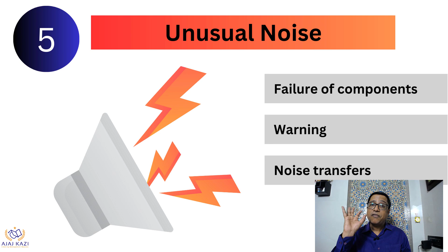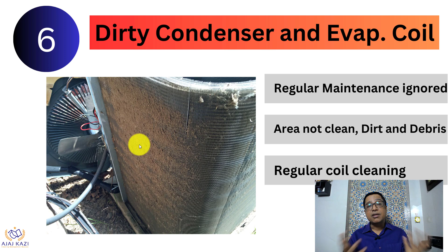The sixth one is again the dirty condenser and evaporator coil. When I talk about the condenser, go and check your outdoor unit and you'll find your entire coil is dirty. This is a major problem. Similarly, open up your inside unit and you'll find your coils are dirty. This is because regular maintenance is ignored. The area where the units are installed is not clean, and hence the area needs to be cleaned, there has to be regular maintenance and regular coil cleaning. This is because the smallest particle can go and attack these coils. You can see over here, full of dirt. The system will start underperforming and it will give way after some time.